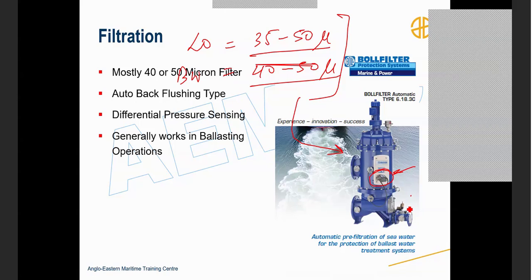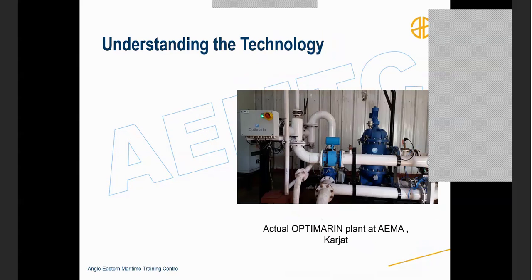Also in the downstream, we have got one pressure transmitter, PT, that will be giving signals to the PLC. So all these mechanisms are fitted. Here this is a motor which is rotating the filter element for backflushing. Okay, this is one of the technologies available.